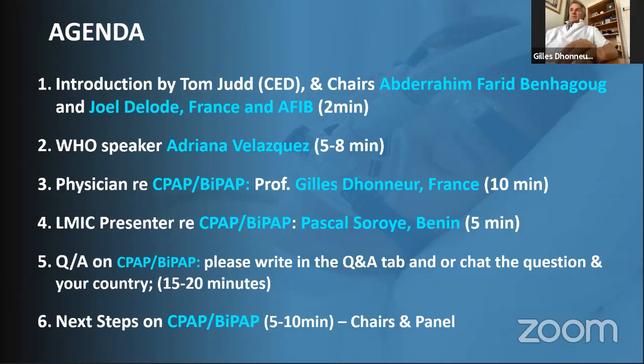Yes, and once again, I'm sorry. If you have a machine, a ventilator, you can control the pressure. So you give the oxygen with an inspired concentration that you can control, and you can control the pressure during breathing. This is one of the systems. But if you have no ventilator, let's use the CPAP of Boussignac. It's an open system. There's never overpressure. Never. If the pressure is too high compared to the patient's thoracic compliance, the air goes out of the CPAP device. It's open, so there's never overpressure.